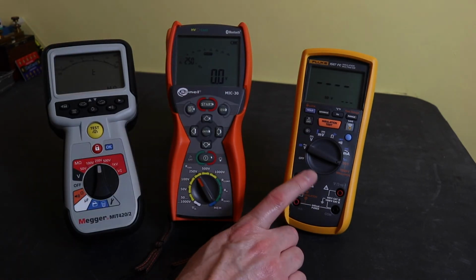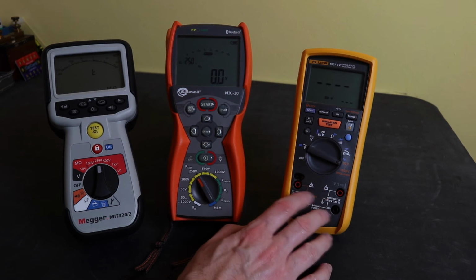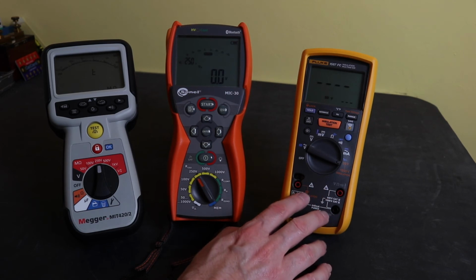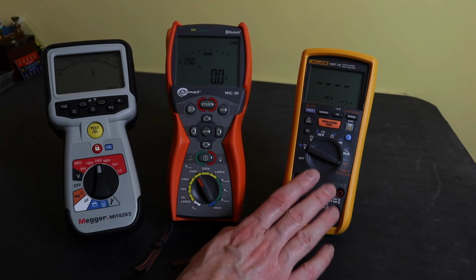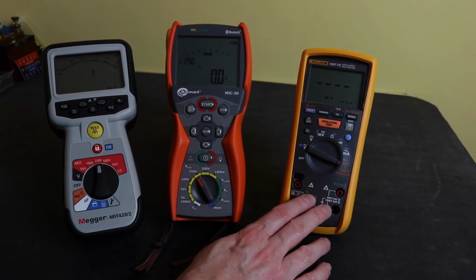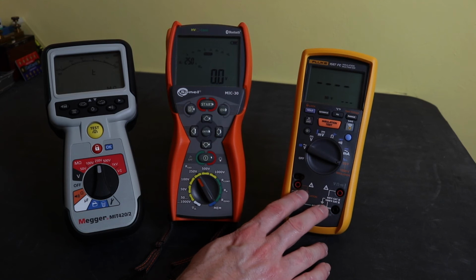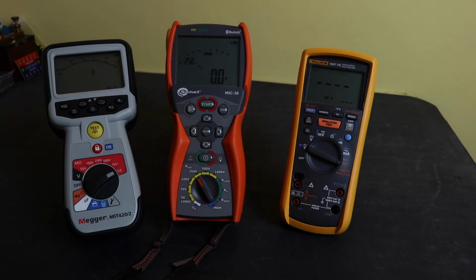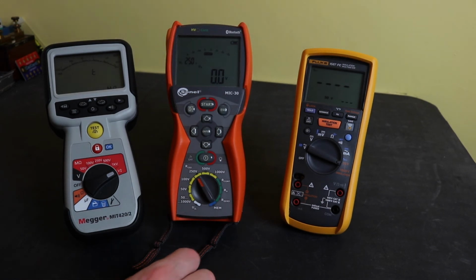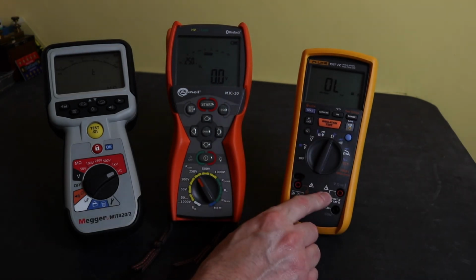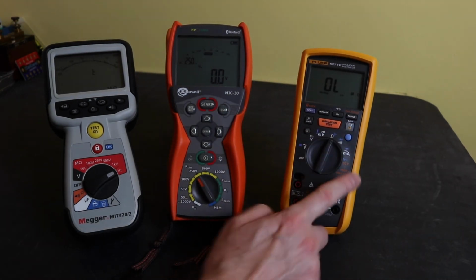The Fluke instrument in that respect is quite a poor test range for insulation test and resistance, and to my mind, for the systems I work on, it is just not capable of doing trending on modern day insulation systems. Go no-go testing it's fine with, but trending actual insulation resistance values, it's a poor instrument for. So let's turn him back to auxiliary functions. For the Fluke here, you have ohms and capacitance.